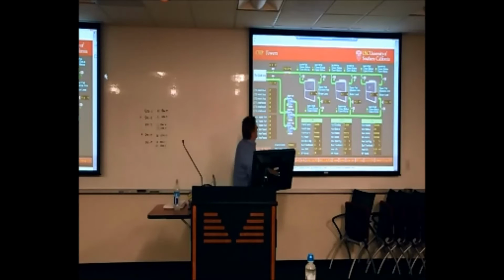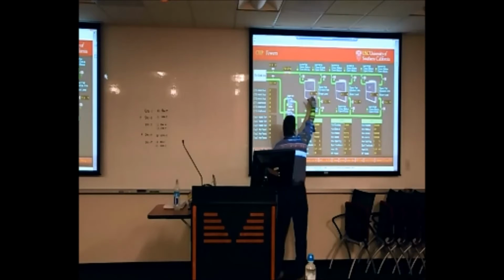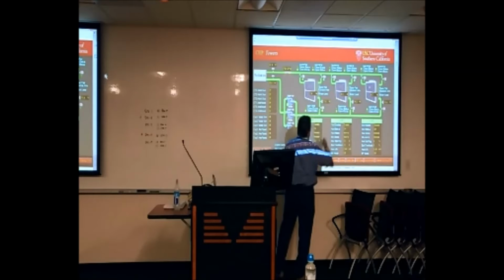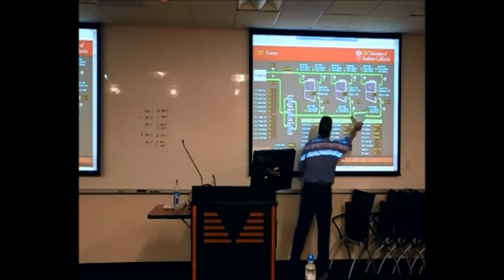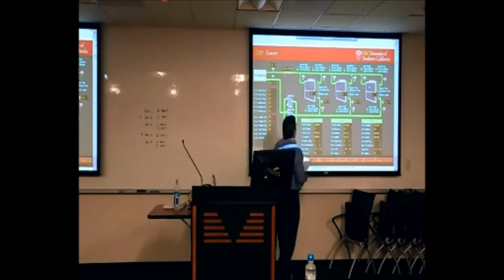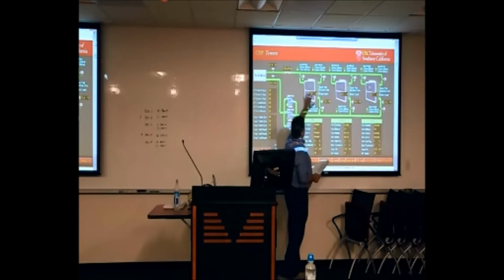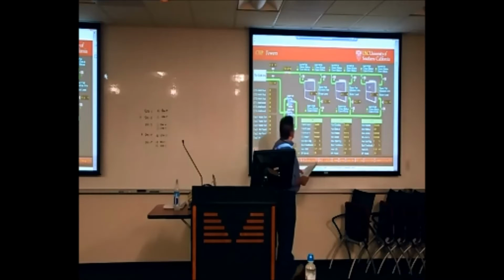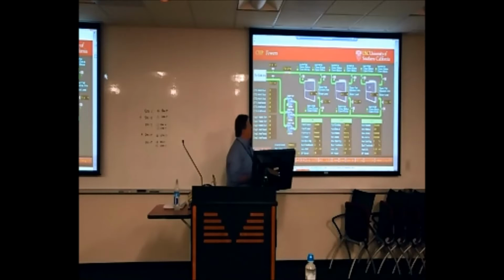We do an alarm on the sensor, so if our water level were to go low, 0 should be the normal water level. So we want to be hovering around 0 if we're at the normal water level. The overflow on this is quite high. I think it's around 8 or 9 inches. So if we pick up to around 8 or 9 inches, we'll get the warning, and then at 9 inches we get the alarm, and that's just about what the overflow location is.